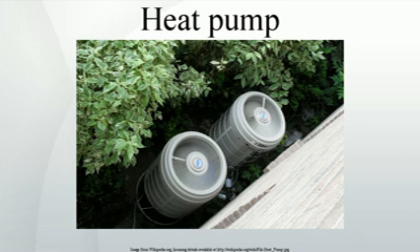The trade-off for this improved performance is that a ground source heat pump is more expensive to install, due to the need for the drilling of boreholes for vertical placement of heat exchanger piping or the digging of trenches for horizontal placement of the piping that carries the heat exchange fluid, water with a little antifreeze. When compared, groundwater heat pumps are generally more efficient than heat pumps using heat from the soil.